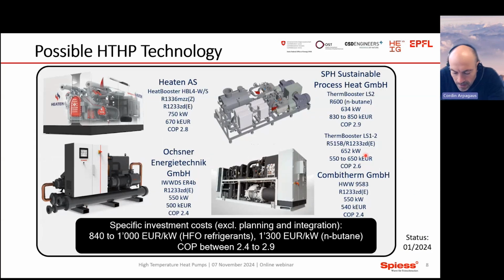So we looked at the possible heat pump suppliers. Here you see 4 examples from Heaten, Ochsner, Combitherm and SPH. And these have synthetic refrigerants for their heat pumps. They all provide 115 degrees and could produce steam at that temperature. Here you see also the rough cost estimations and the COPs for these temperature conditions. From SPH, we could also get an offer for a butane hydrocarbon solution.